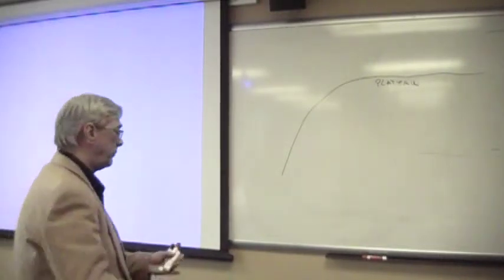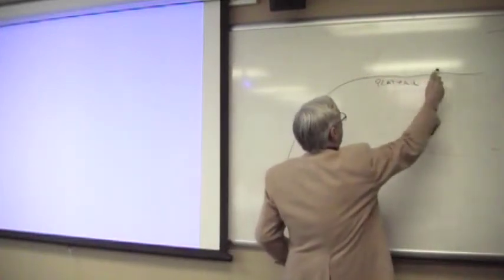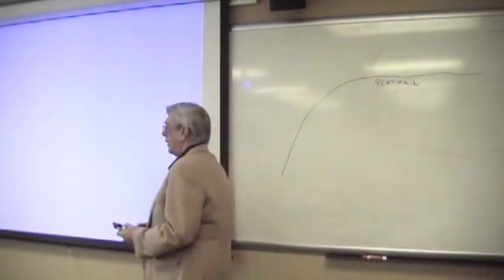What we're looking for is for the rate of increase to slow down to, I think, not greater than 2% per second, something close to that. Once it slows down to that point and the person stops blowing, you'll get a sample, provided you've also satisfied the minimum requirements early on—which, if you get up to that point, you have.